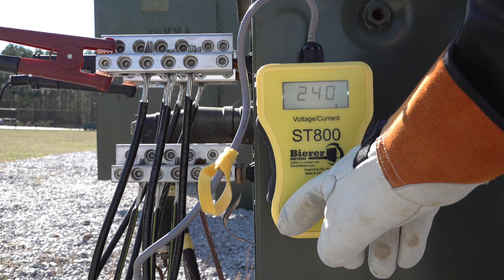In the V position, or voltage position, the ST800 should read 240 volts. By connecting the black lead and the red lead to both hot bushings of the pad mount, we maximize the turns ratio of the transformer. This means that once the ST800 achieves 800 amps on the secondary side, it will maximize the available current to identify on the primary side of the transformer.